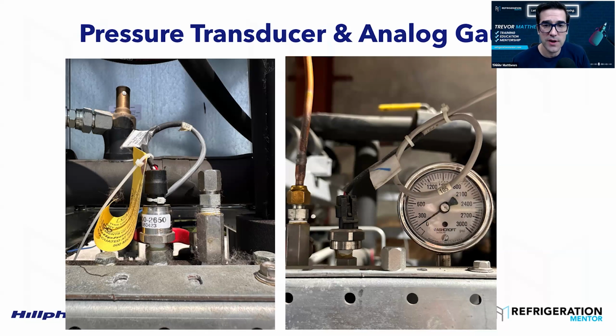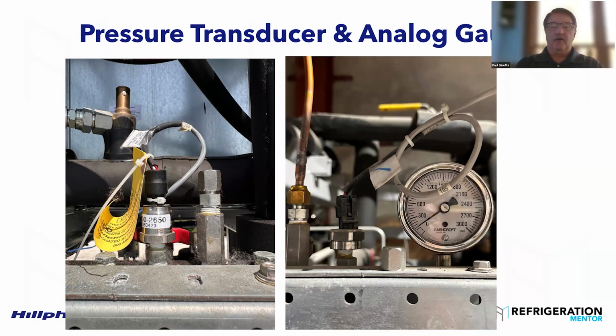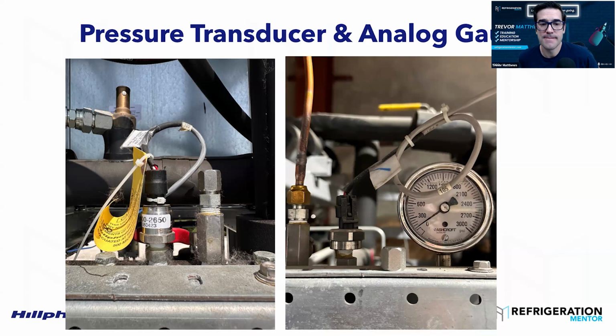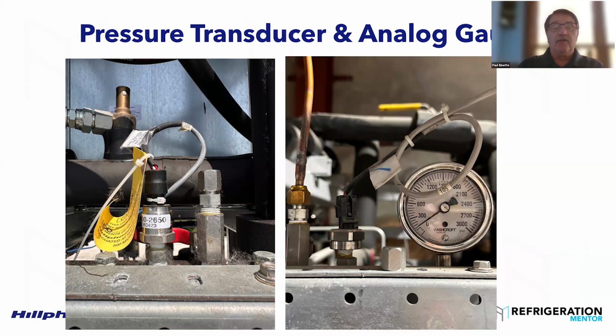So on this slide, we're seeing some pressure transducers, an analog gauge. What do you want to talk about here for startup and commissioning? Yep. The reason I put this in here is that one of the main startups that I take care of, but should be the contractor's job, is you have to verify everything on the rack. You have to make sure that the medium temp suction transducer or medium temp suction temp sensor are actually wired to that, because they're really close to each other on the control boards. It's not hard to make a mistake. So we verify all this prior to startup. We check our transducers, we pop them off, make sure the one off is the one that's going down on the control board. I don't care what it is, Carel, Micro Thermo, Danfoss, Copeland, they all have inputs.